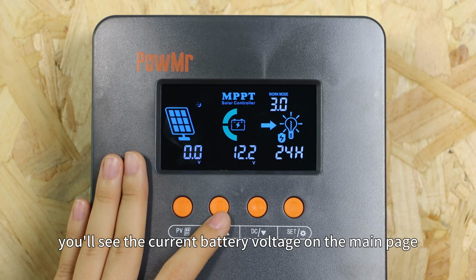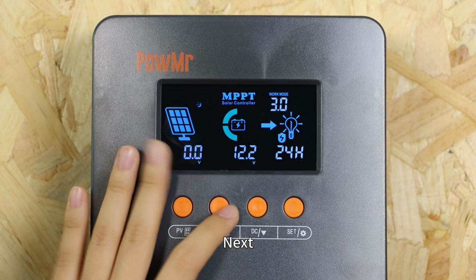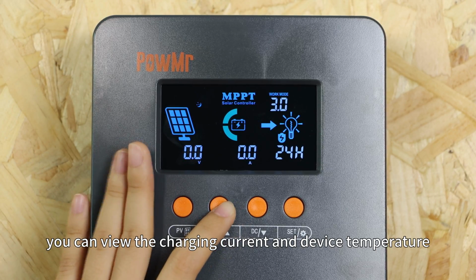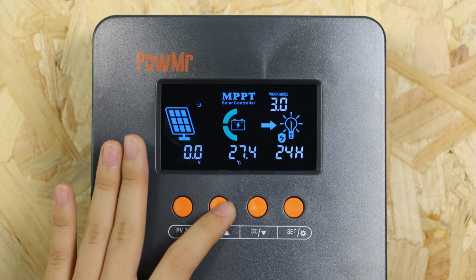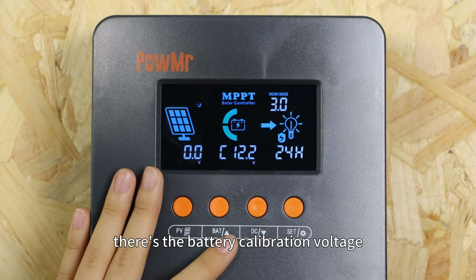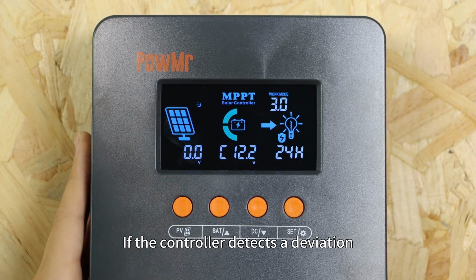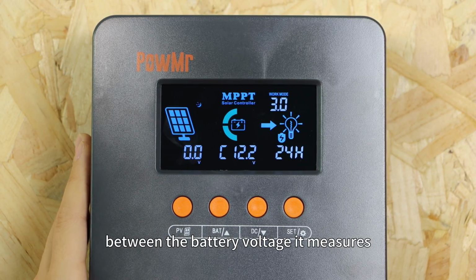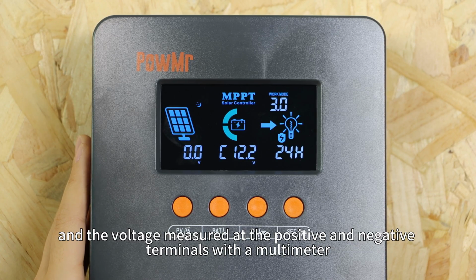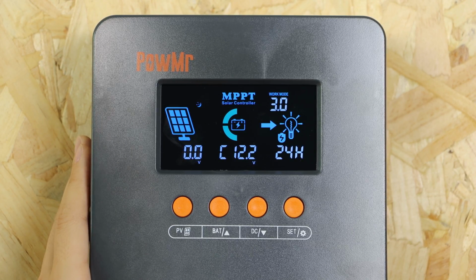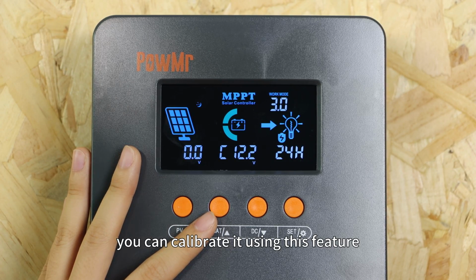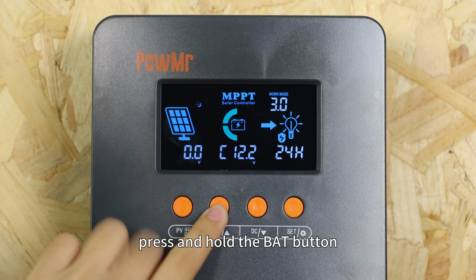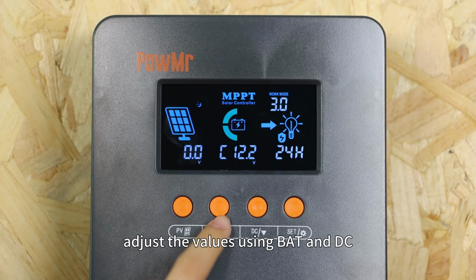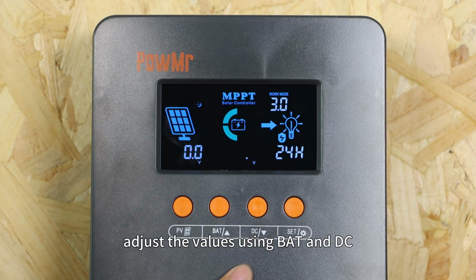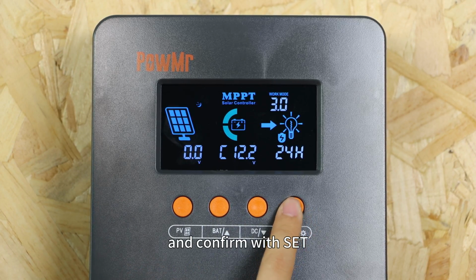First, you will see the current battery voltage on the main page. Next, you can view the charging current and the device temperature. Then there is the battery calibration voltage. If the controller detects a deviation between the battery voltage it measures and the voltage measured at the positive and negative terminals with the multimeter, you can calibrate it using this feature. To calibrate, press and hold the battery button, adjust the value using the battery button and DC button, and confirm with the set button.